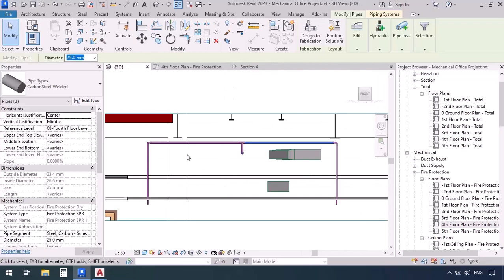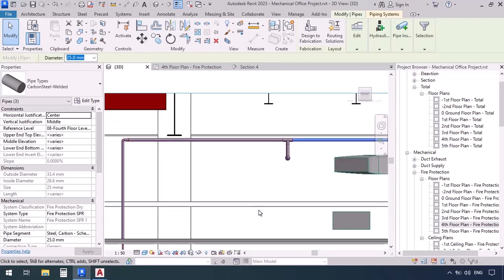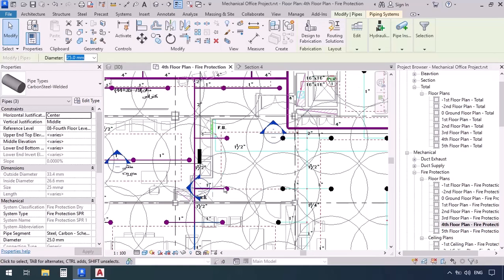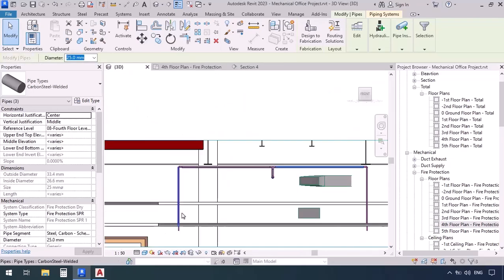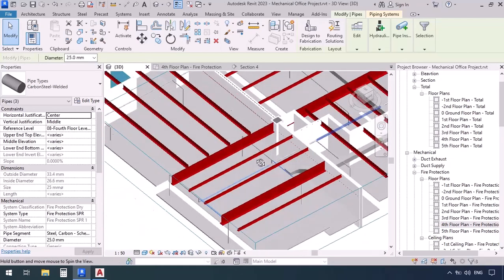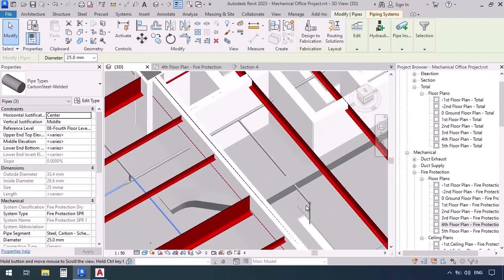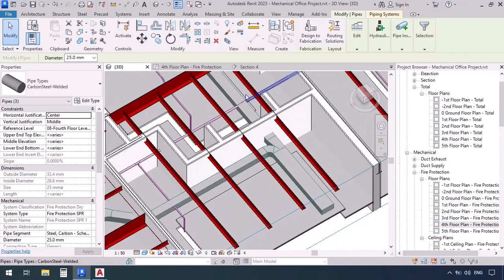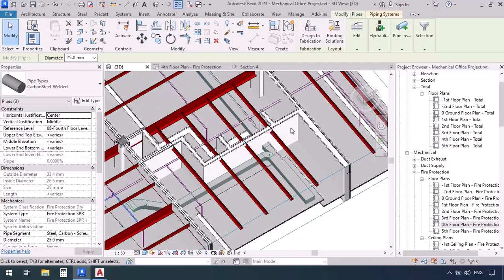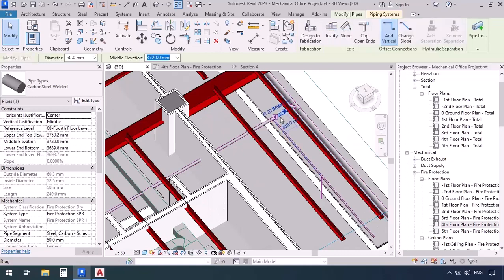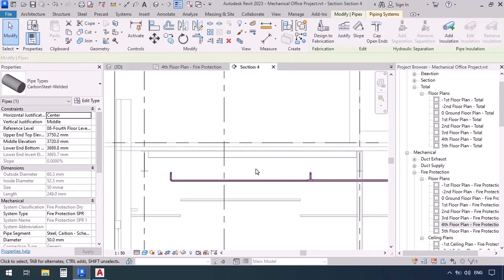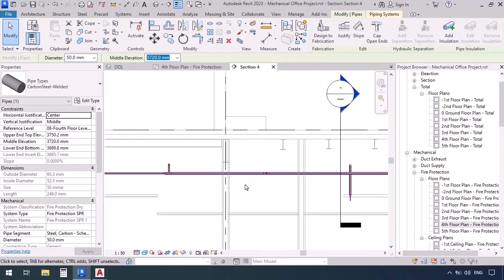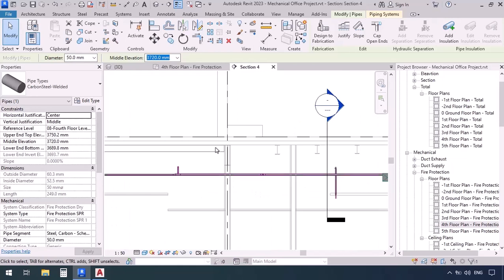We're gonna double check in 3D and as you can see we still have enough space to make it higher. Now we are at a proper elevation where the pipe is going below the beam. So we've taken care of these first two. Now let's go in 3D and rotate our view. So we're done with these two and this pipe went lower. But now that it did go lower it's crossing the duct. What about this part? This one's also going through the duct. So this wasn't a proper solution. What we had already done before and made the elevations 3,900 was better. So instead we're gonna focus on here on this part. First let's go to section.